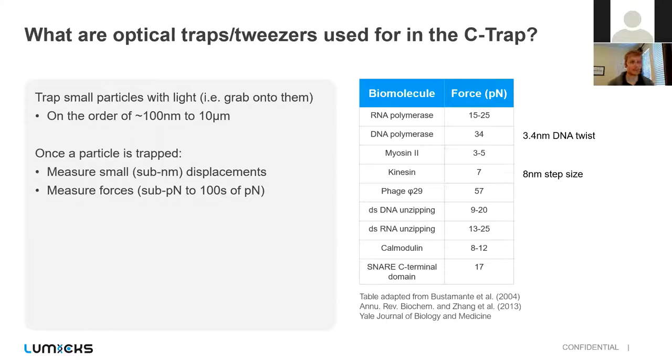And so for the C-TRAP, you can't necessarily trap atoms, but you can trap small particles on the order of about 100 nanometers to 10 microns. And once you trap a particle, you can measure very small displacements, so sub nanometer displacements, as well as both sub piconewton forces to hundreds of piconewtons of forces. Some of the examples I'll show today demonstrate this range of displacement force measurements. And why this is well suited for studying biological systems is because if you look at things like DNA polymerase, or maybe your kinesin motors, you'll see that they have forces on the order of piconewtons. And then you're dealing with step sizes that are often on the order of nanometers.